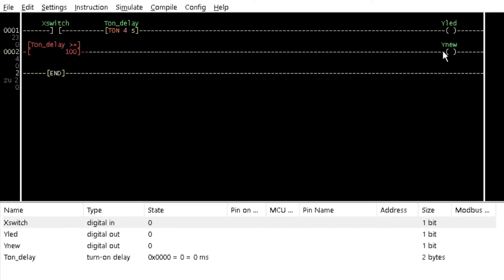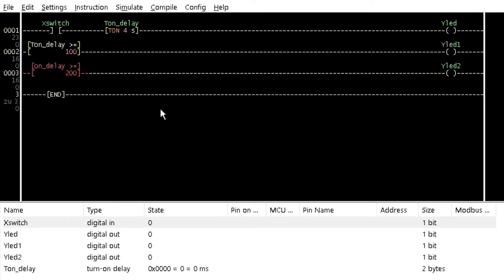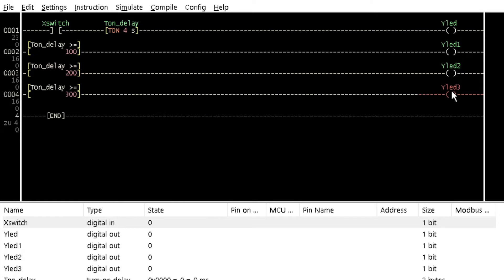Also, insert a coil on the same rung and name it Yled1. Repeat the previous steps in two additional rungs using the same timer variable name, but with the greater than or equal values being 200 and 300 respectively. Name their coils as Yled2 and Yled3 respectively. Simulate the program and double click on X switch to activate the timer.